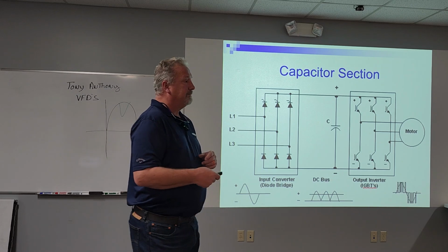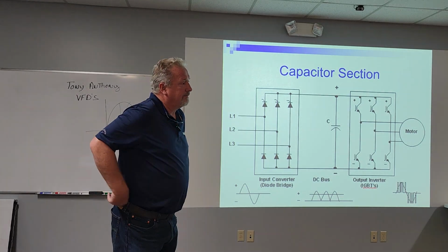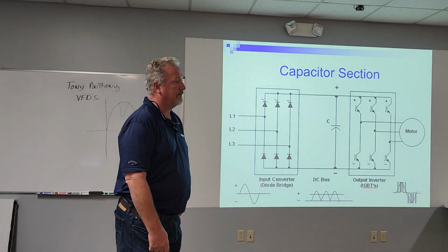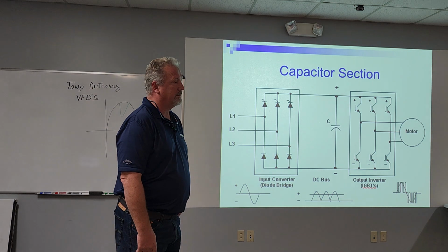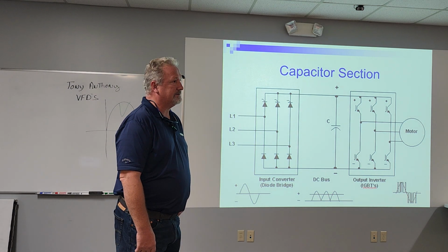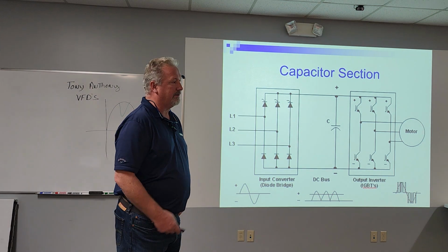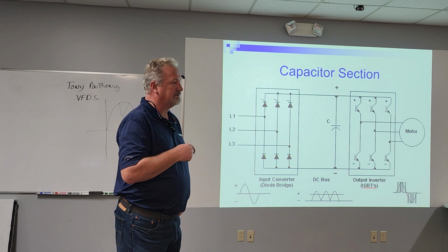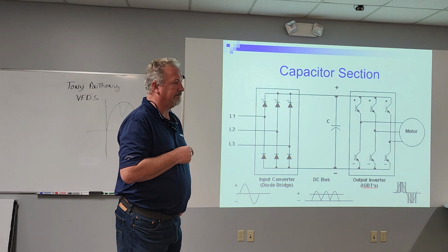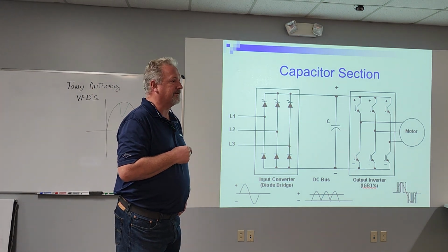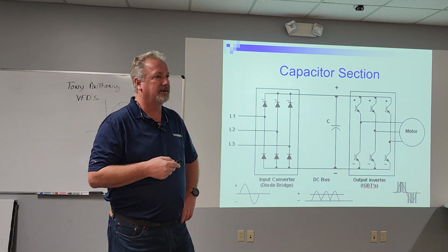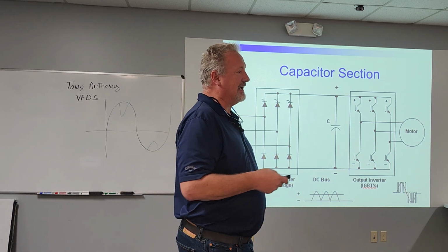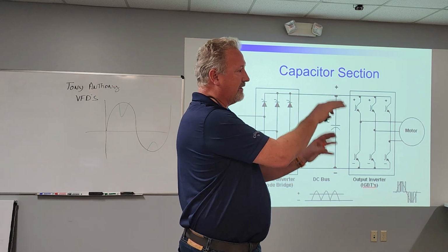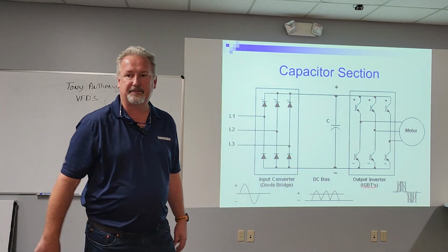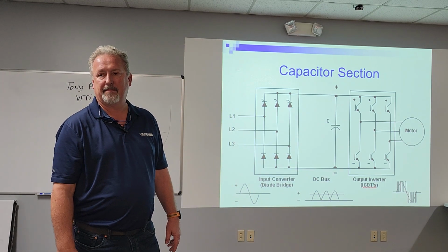So basically, that's how a phase monitor is monitoring the phase, just by checking for that 1 volt. Not on the drive. No, the drive. But I'm just talking about a phase monitor in general. No, no, it's a different thing. It's altogether different. It's checking actually the phases, not the DC bus. It's actually checking each phase. The monitors we use are ICM, and they're phase-to-phase protection.